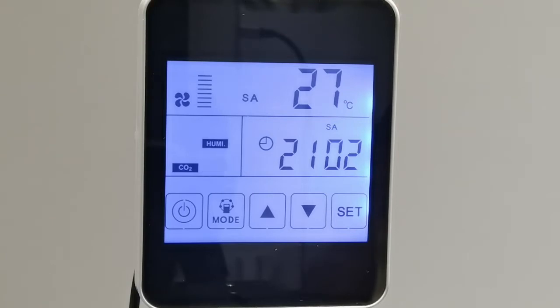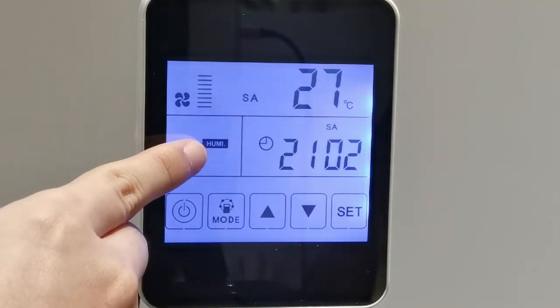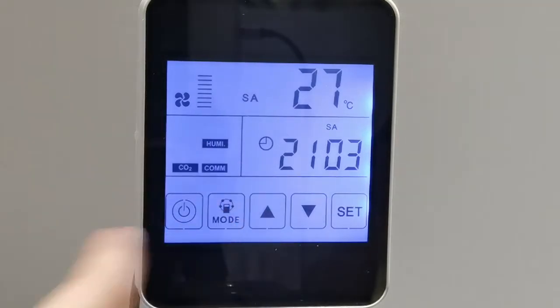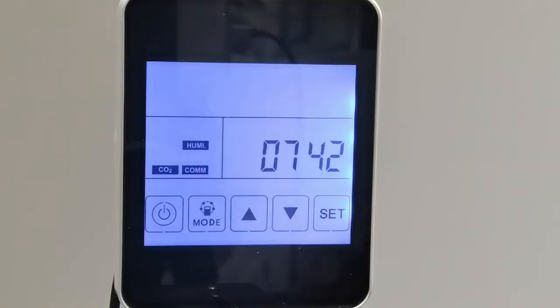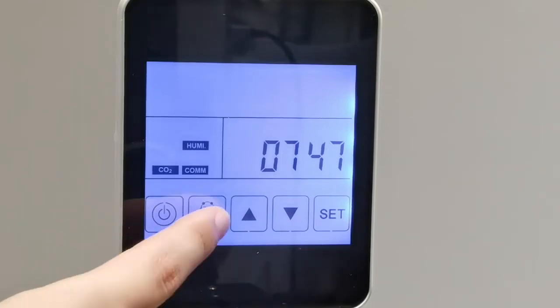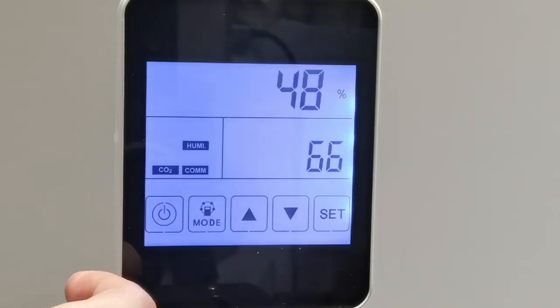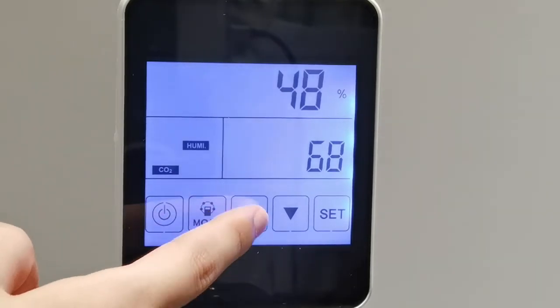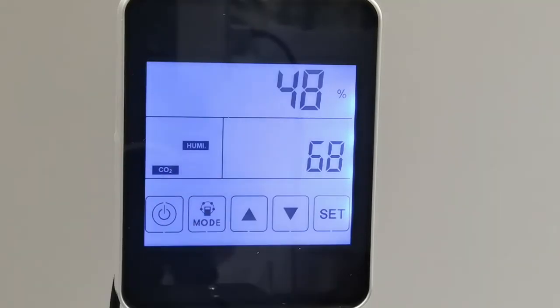And there is a humidity symbol that appears when the humidity sensor is connected with the ERV. When humidity is higher than the setting value, the ERV will run at highest speed automatically until the humidity is down below the setting value. When setting the humidity, we can adjust it by pressing the mode button and the up and down buttons. Okay, the setting range is 45% to 90%.